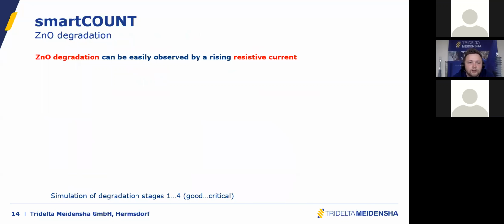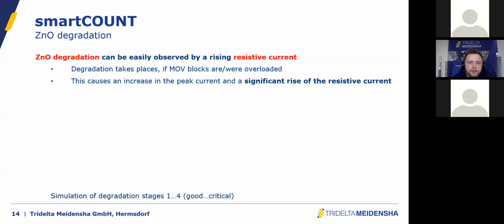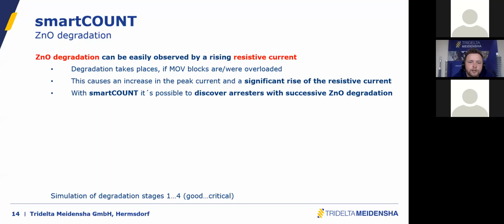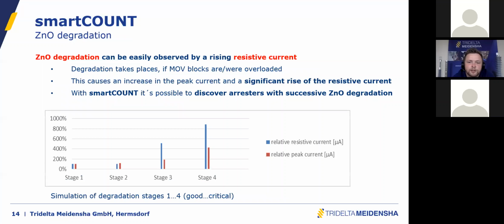At first, of course, zinc oxide degradation. This can easily be observed by a rising resistive current, and this is the only case where we have a continuous rising resistive current. This happens due to degradation of the MOV blocks, and this might be due to an overload of the MOV blocks or some mistakes during manufacturing, which shouldn't happen if you're a good manufacturer. And the result from this is an increase of the peak current, but a significant rise in the resistive current. And with the smartCOUNT device, we have the possibility to discover this, and I show you how.